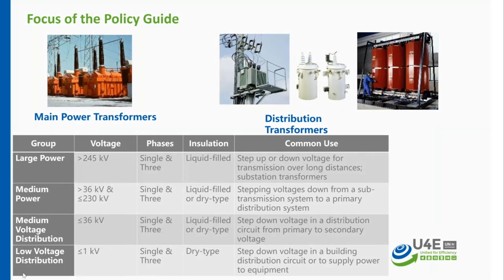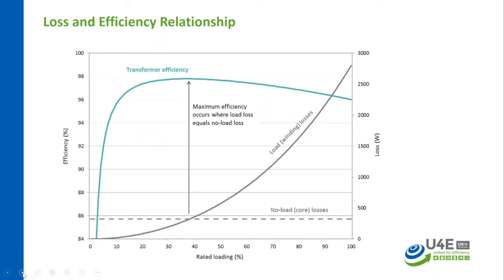As you know, the efficiency of these transformers can be addressed in two ways. Currently, as you know, the distribution transformer has two components of losses. One is the no load loss, which is the constant loss where energy is consumed and heat is generated 24/7. And the second one is the copper loss or winding loss, which is the load loss, directly proportional to the square of the load. So as the loading increases, the importance of load loss becomes very vital. And having a transformer with lower load losses is going to run the transformer cooler, making it more compact, etc.